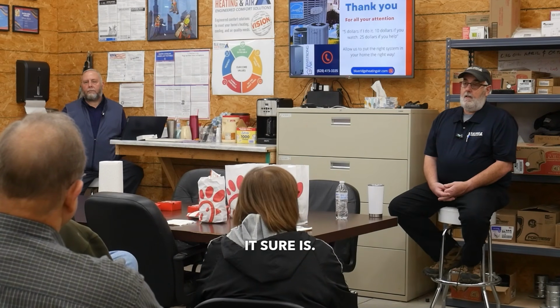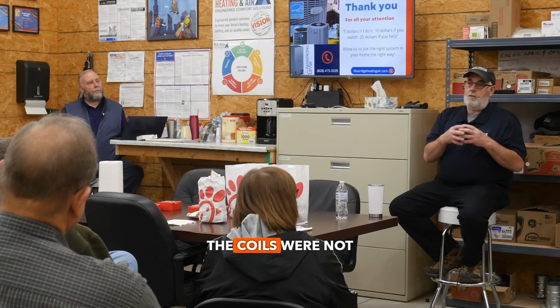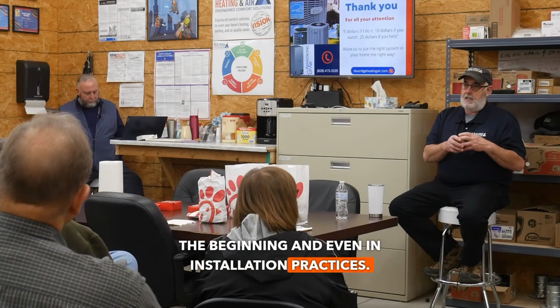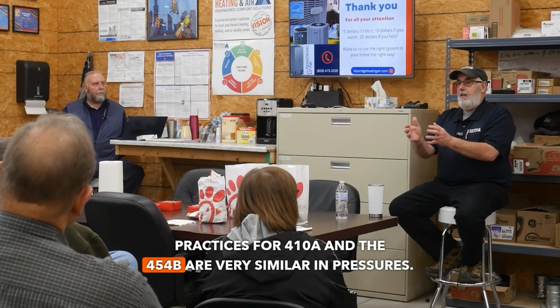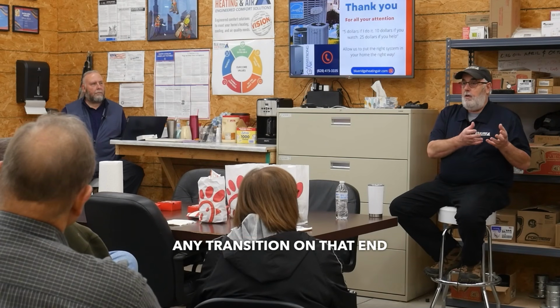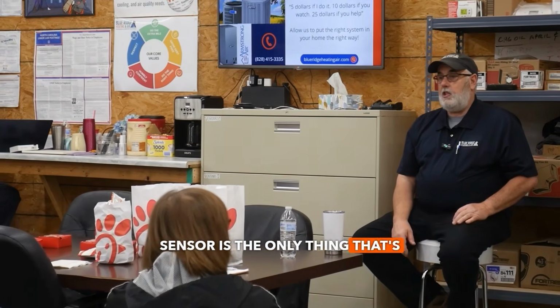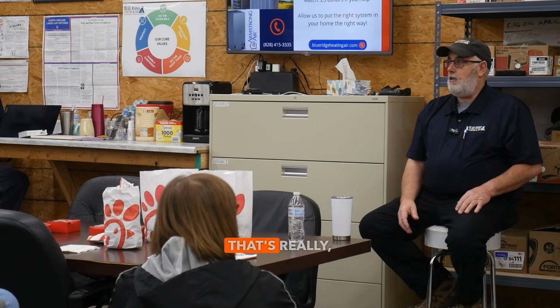It sure is. But at the same time, I just lost my thought. Going from R-22 to 410A, the pressures went from such and such to very high. So the metal, the copper tubing, the coils were not on board with that. So we had a lot of coil leaks in the beginning, and even in installation practices. So now we already have the installation practices for 410A, and the 454B pressures are very similar. So there's not going to be hardly any transition on that end of it for us or for many companies around. The only issue I think is the sensor is the only thing that's changing, and the refrigerant's changing, and the compressors will have to be compatible for that new refrigerant. That's all it's down to.